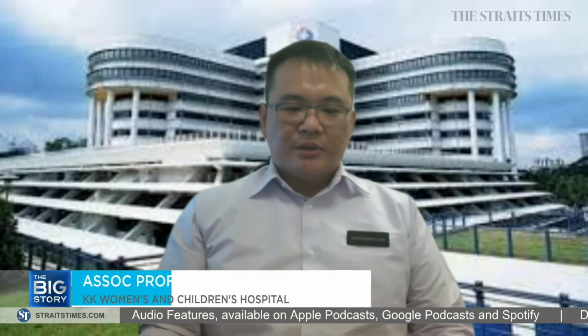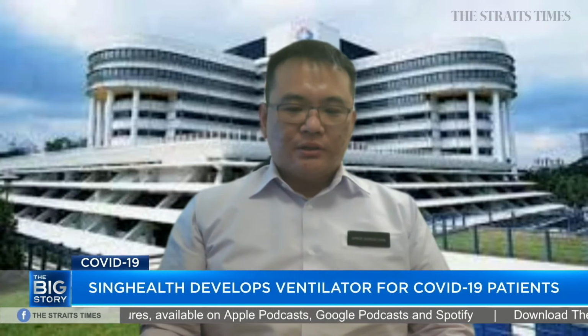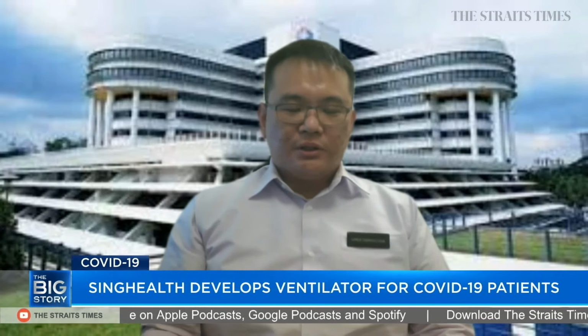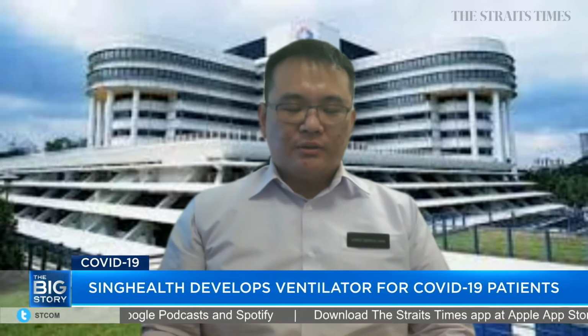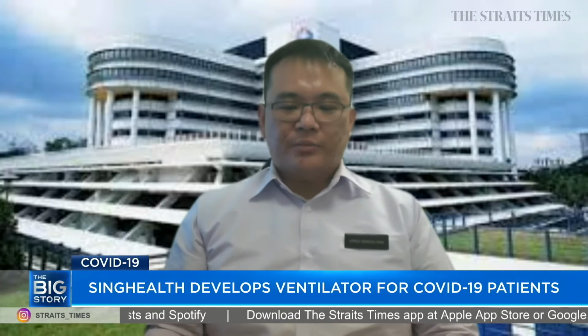Now, Prof. Chan, let's bring you in on this discussion. How is this ventilator different compared to the ones already in the market? In other words, why is it more user-friendly than conventional ventilators? So this ventilator is designed to supplement conventional ventilators. It's basically meant to assist with the COVID pandemic situation, and essentially has the design features that it can be using a simplified interface, so people with less training can use less settings and basically still achieve the same result for patients.